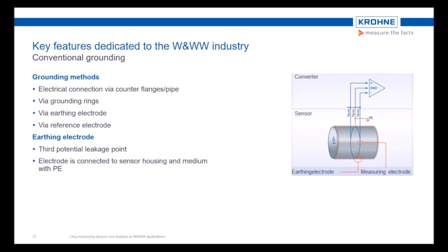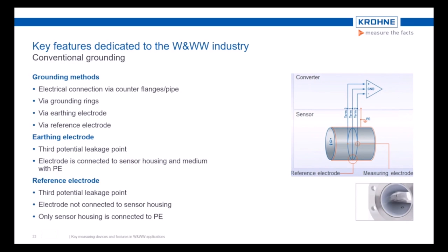Alternative methods to grounding rings are earthing electrodes, which may save money, but on the other hand bring an additional risk for a third leakage point. In this case, the electrode is connected to the sensor housing and medium with protective earth. Comparable to the earthing electrode, we also use the reference electrode, which may also increase the risk for a potential leakage point, but may also save money compared to grounding rings. So when using devices with reference electrodes, those are not connected to the sensor housing, but only the sensor housing is connected to protective earth.